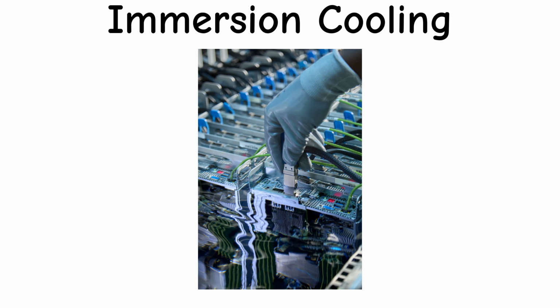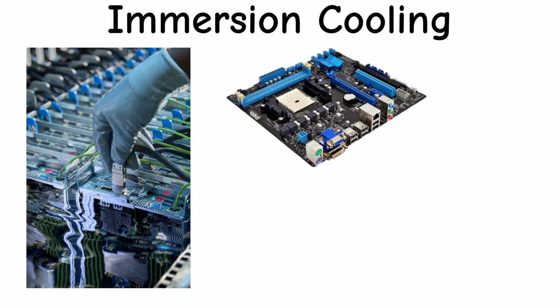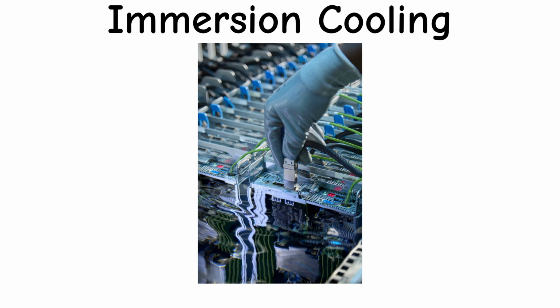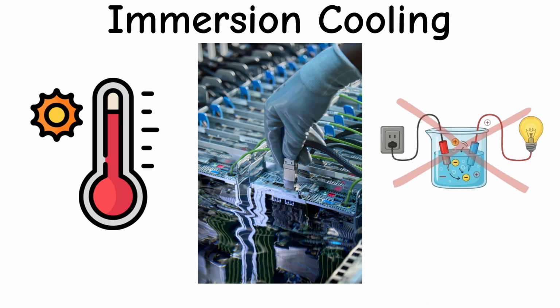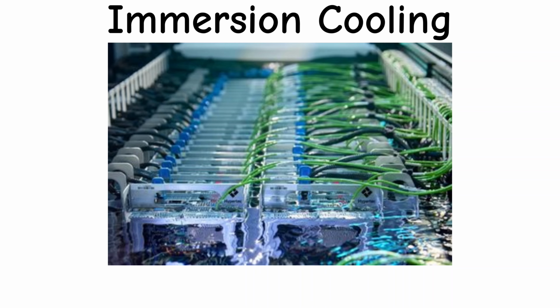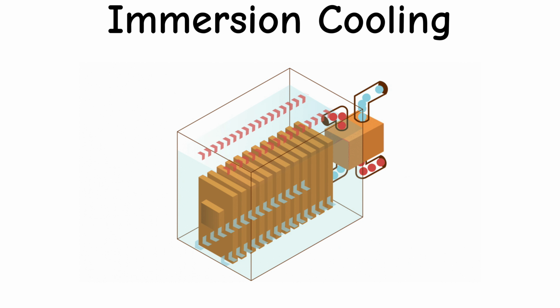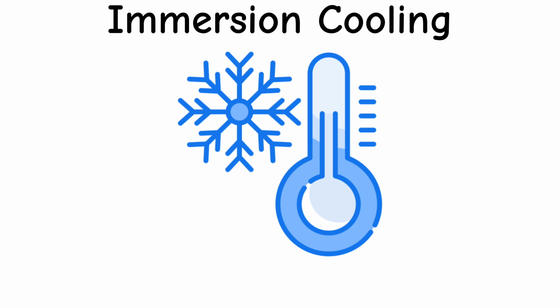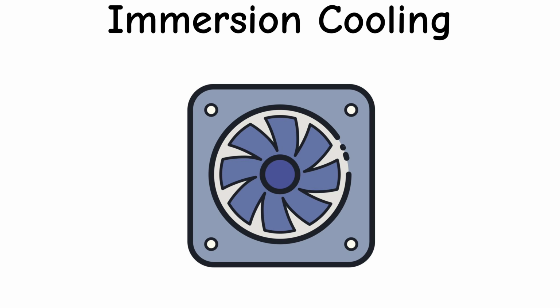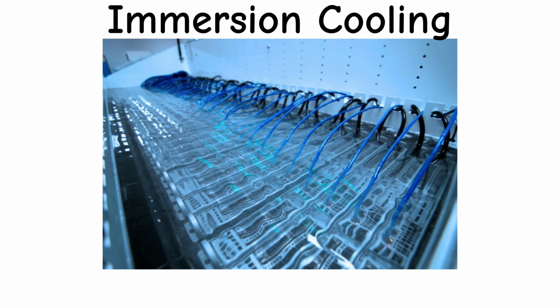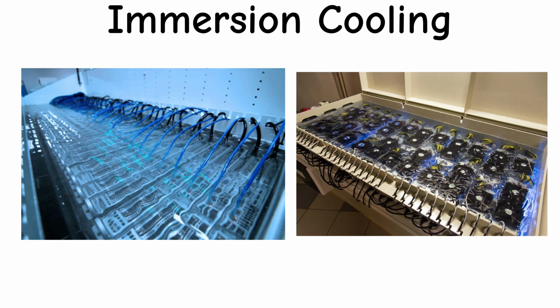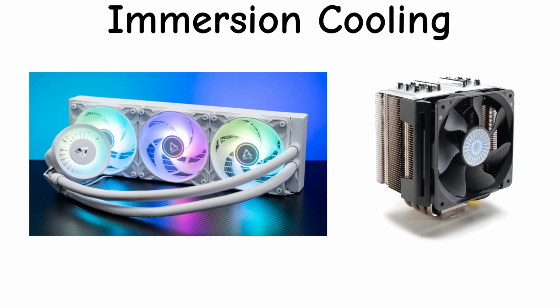Immersion cooling. Immersion cooling submerges the entire system, motherboard, CPU, GPU, and all, into a dielectric fluid that conducts heat but not electricity. The fluid contacts every component directly, absorbing heat from every surface simultaneously rather than relying on airflow to reach them. Heat moves into the fluid, circulates to a heat exchanger, and the cycle continues. The result is exceptional thermal performance at any load level, with no fans and no airborne dust accumulation. Data centers and cryptocurrency mining operations use immersion cooling for hardware that runs continuously at full load, environments where conventional cooling reaches its limits and efficiency directly affects operating costs.